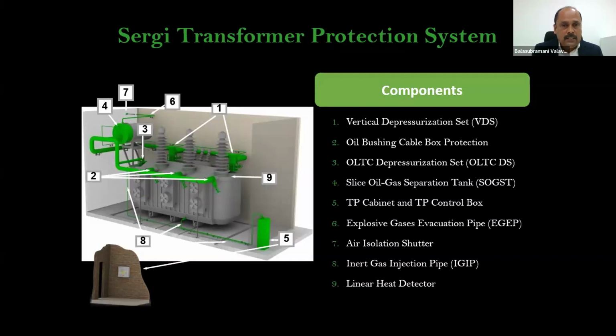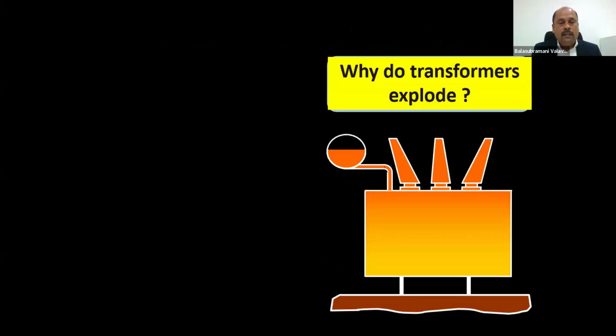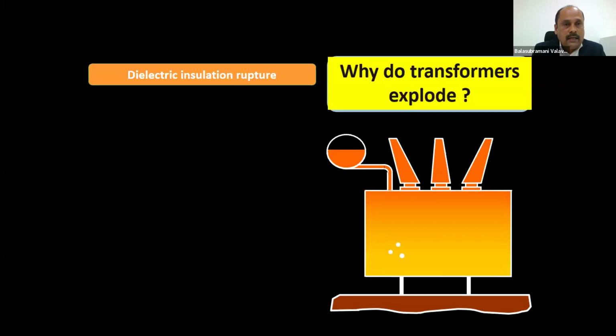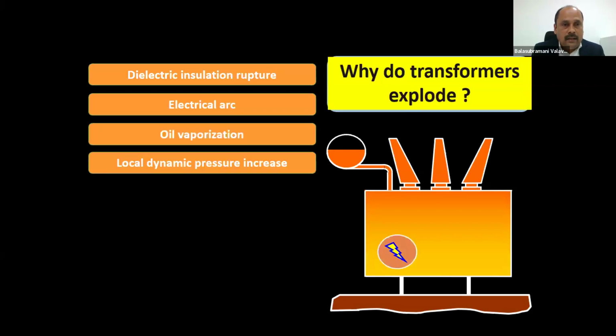What exactly happens is, when there is no SERGI, when there is no depressurization chamber, the dielectric insulation ruptures, which means a short circuit happens. The electrical arc is created. When the arc comes, it will have contact with oil. The moment it gets contact with the oil, it starts to burn. When it burns, the pressure increases. With respect to the temperature, the pressure increases.